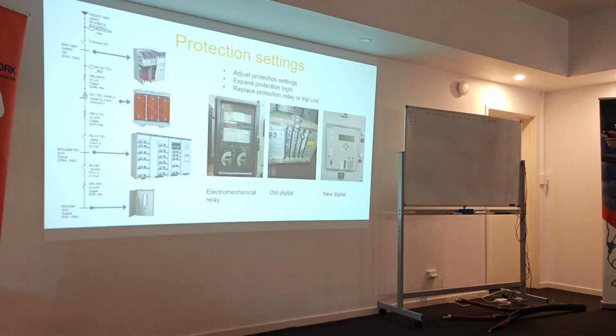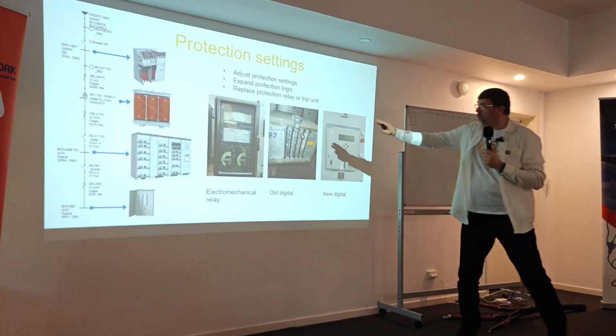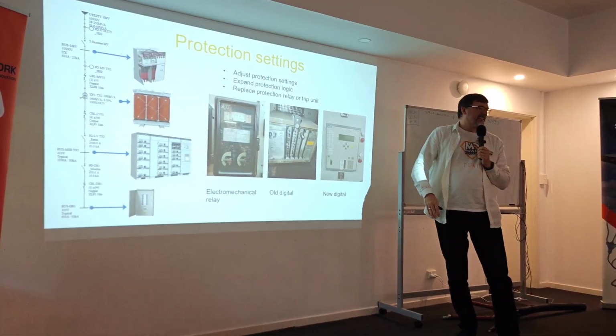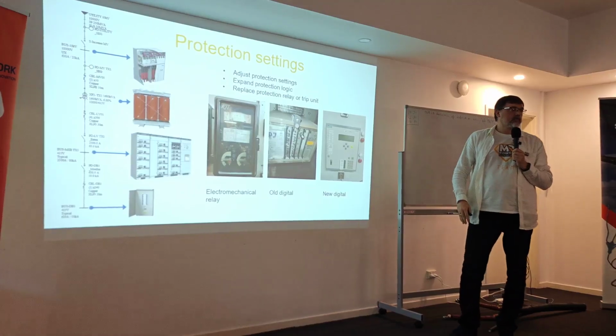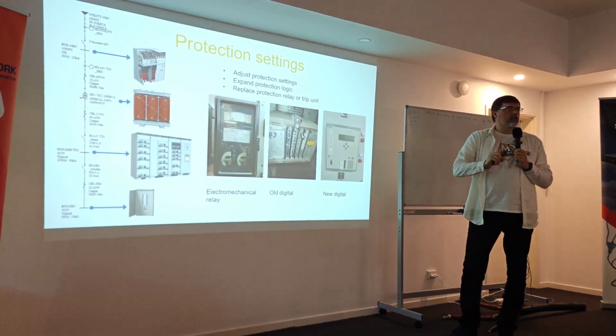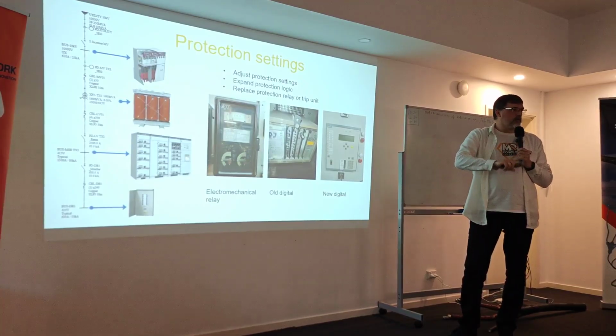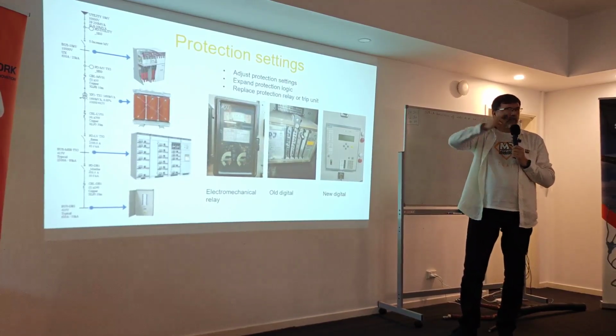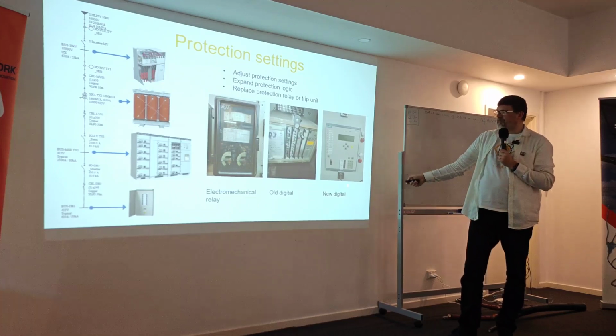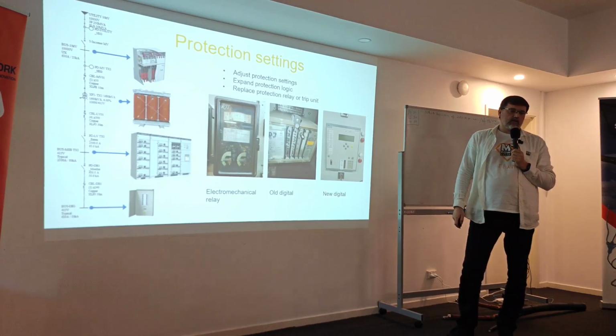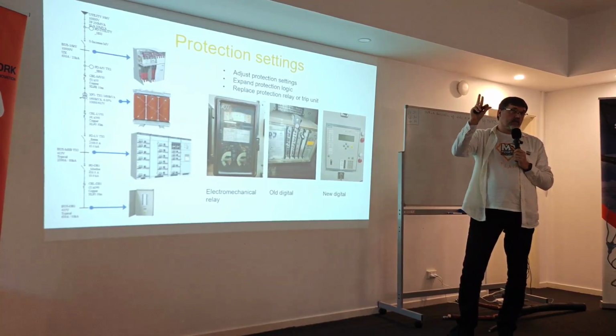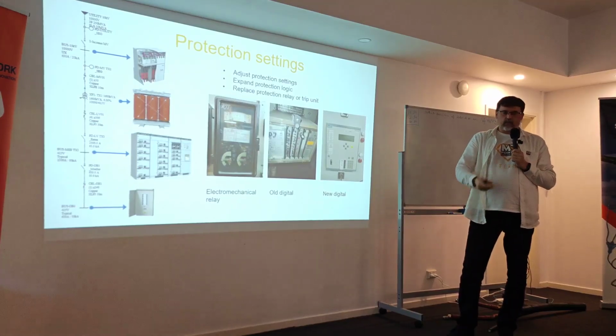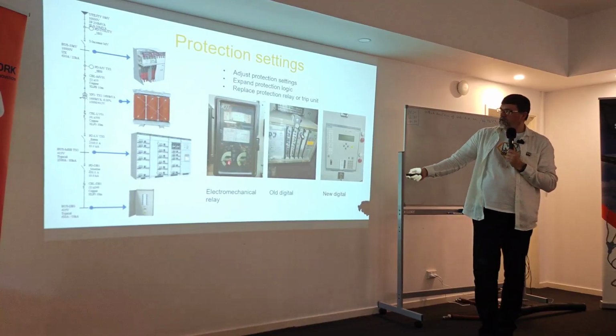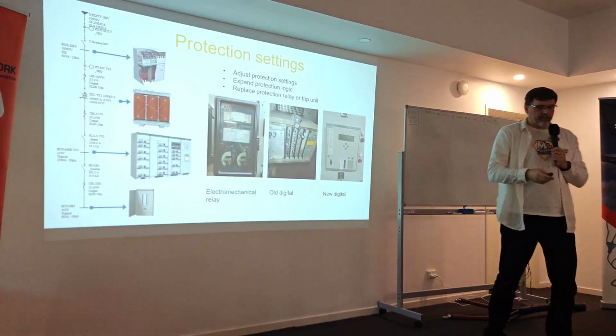So initially, if you look at the protection settings, the first thing is that we need to be allowed to even do any adjustments. Yeah, because sometimes relays are so old or weird. Or they might not even be old. They might be very simple relays, brand new but simple relays. Yeah, so that's the project design thing. It's good when the relay has at least a few steps that you can adjust, or at least 3, and 2 groups of settings that can be used. Well, the controlled way. The old ones are not bad, it's that they just have limited regulation.